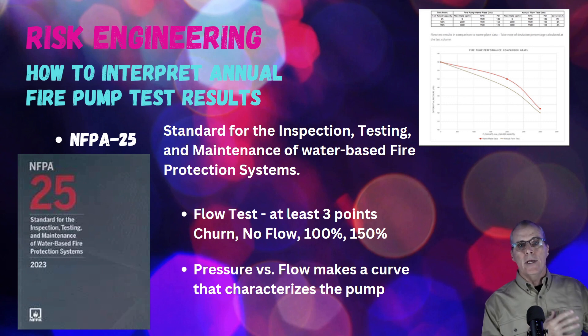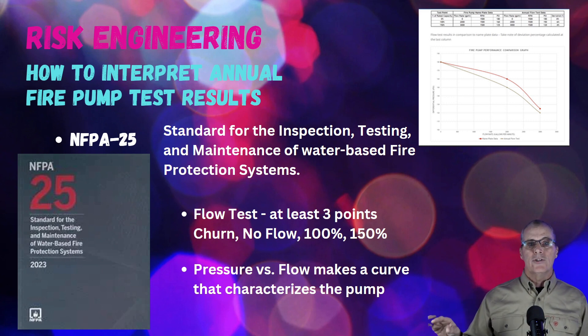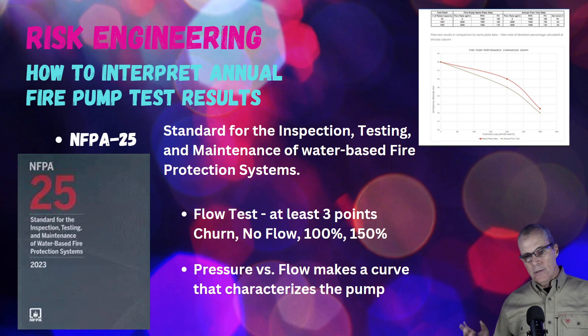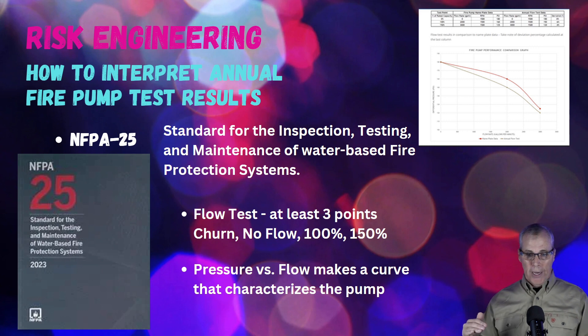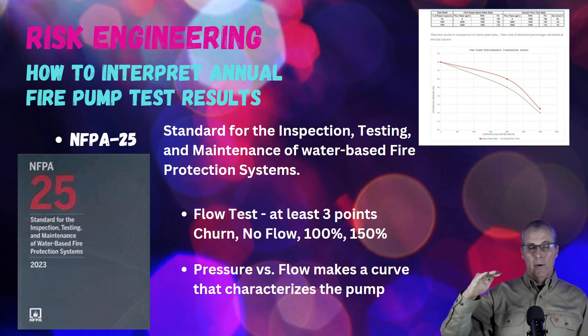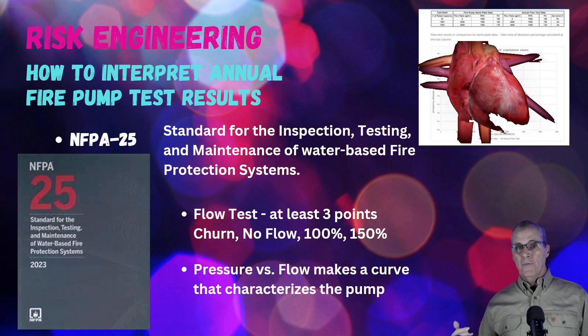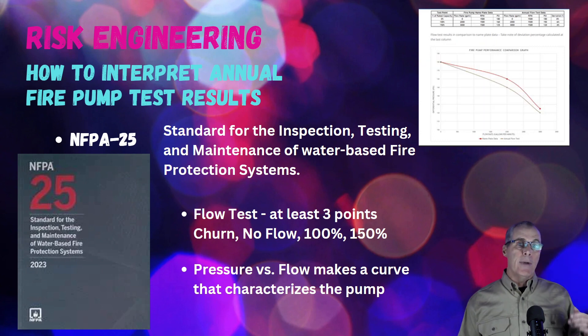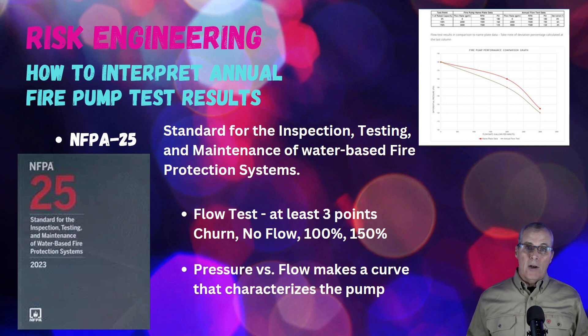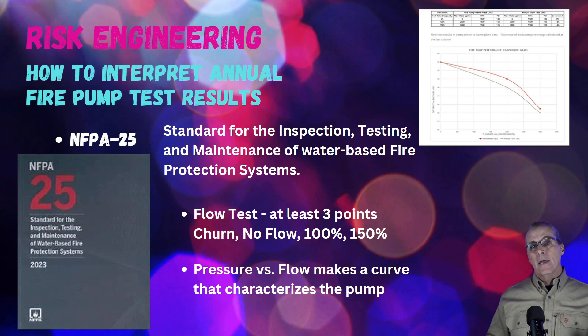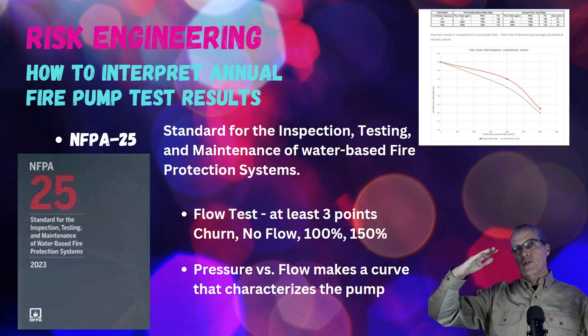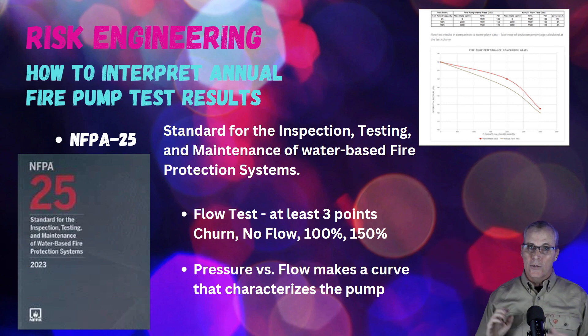In the old days of NFPA 25, it was okay if the pump could put out the water necessary for the largest system demand on site. That has since been changed to compare your results with the original brand-new pump. Whenever your pump is more than 5% below what it was doing when it was brand new, the manufacturers think you need to take it apart, figure out what's going wrong, replace the impeller, and get it back up to 100% of brand-new performance — even if the pump was originally oversized by 50%.